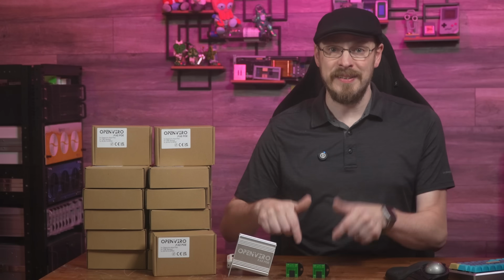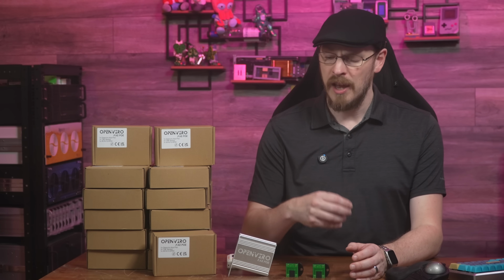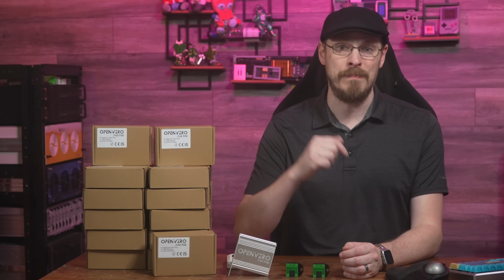As for monitoring the sensors themselves, the Openviro Axe PoE supports SNMP versions 1, V2C, and V3, and utilizes the Entity Sensor MIB. Most SNMP monitoring software is fully compatible out of the box. A few pieces of software, like PRTG, do not include the Entity Sensor MIB by default, but it can be added manually. We will be working on developing templates for installation in the coming months for easier setup and configuration with whatever monitoring software you choose to use.